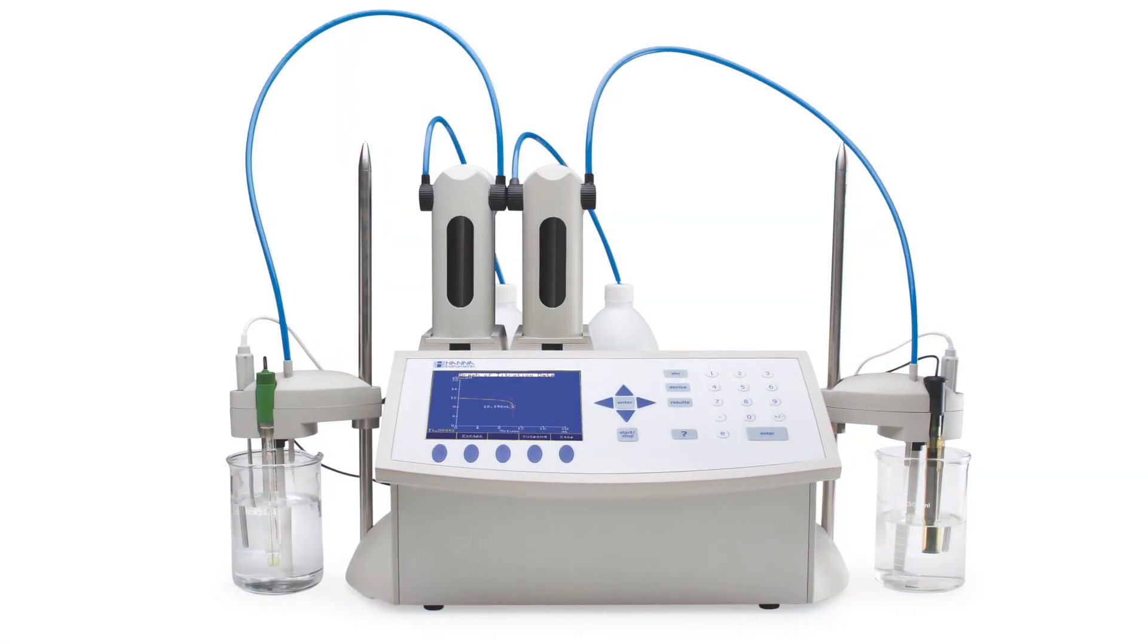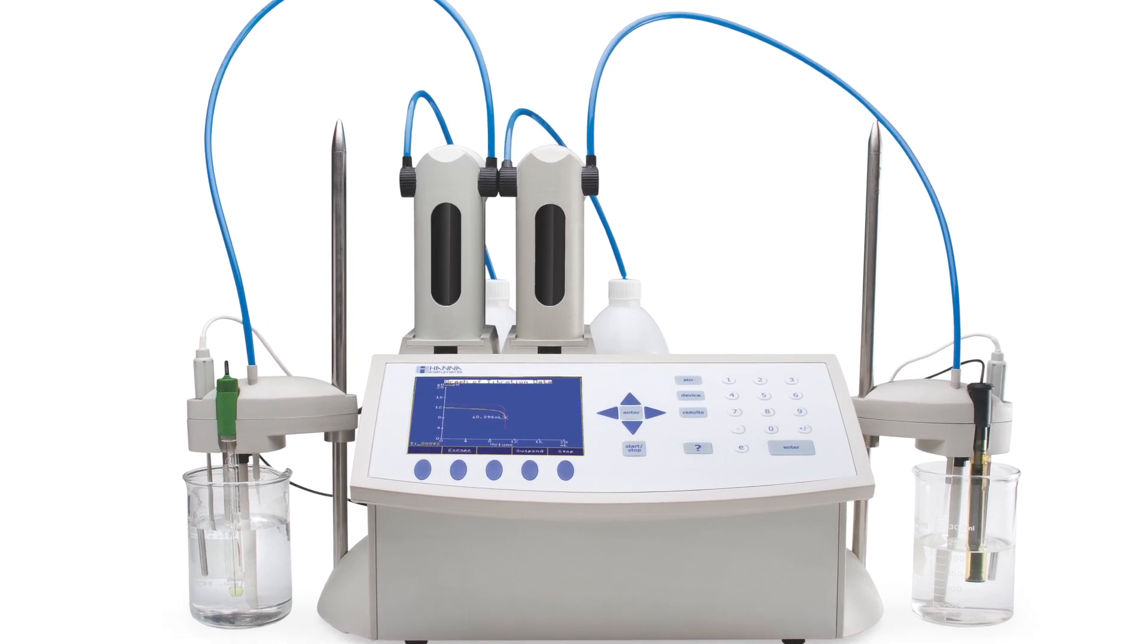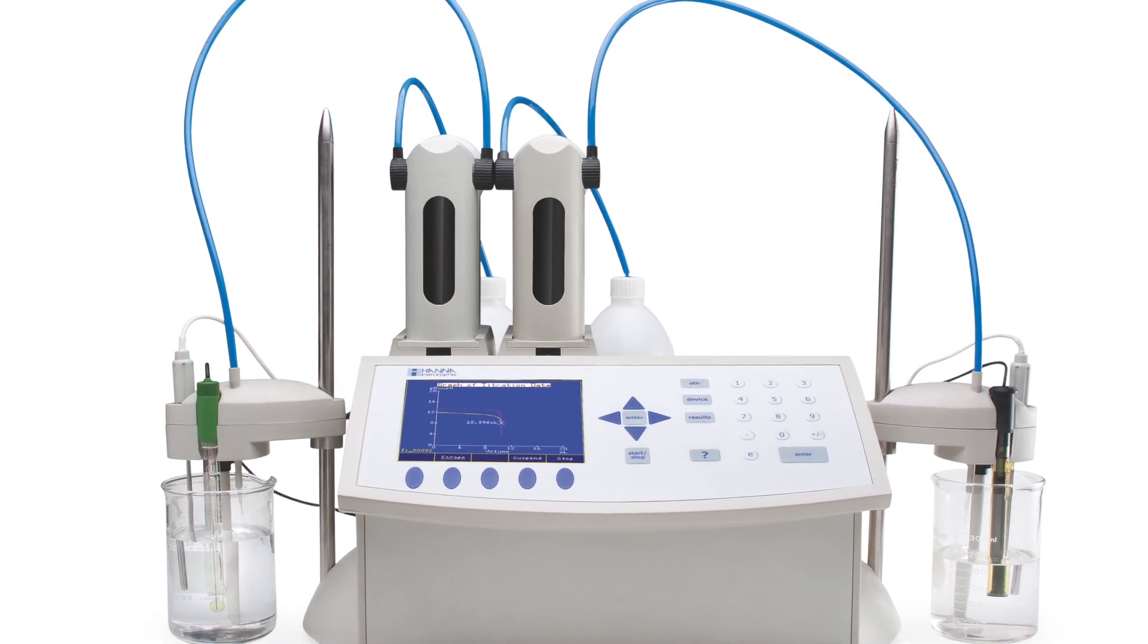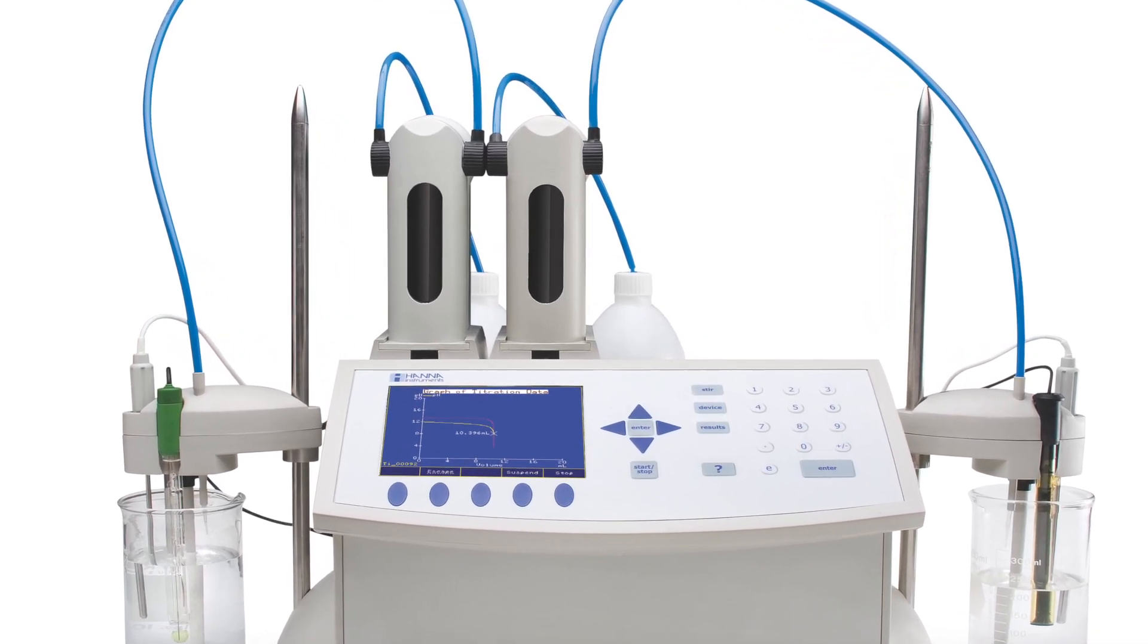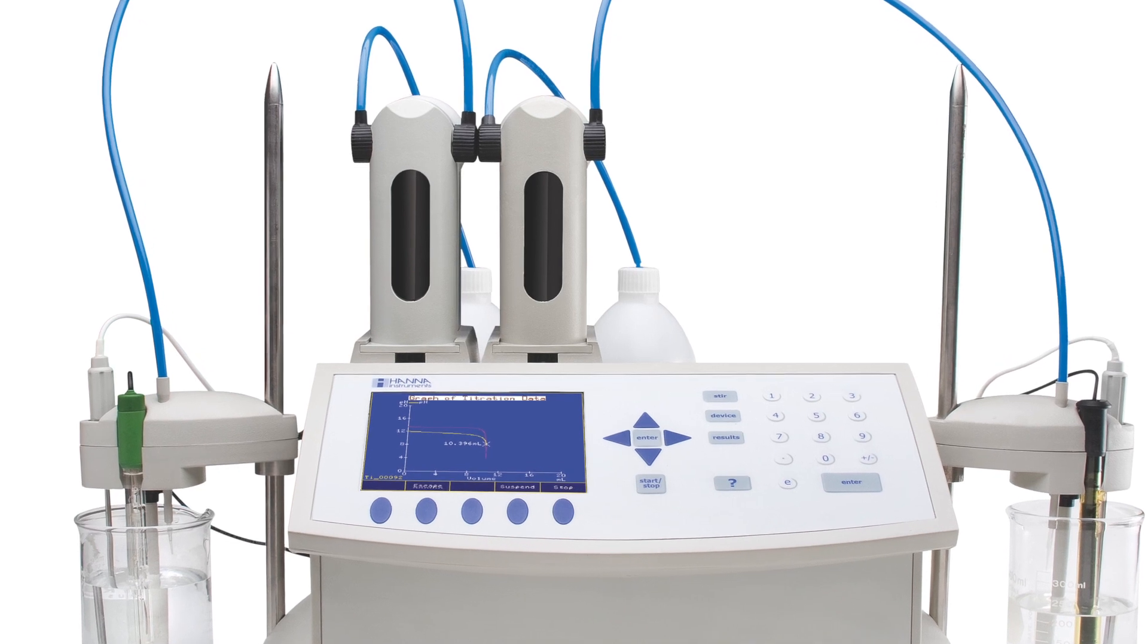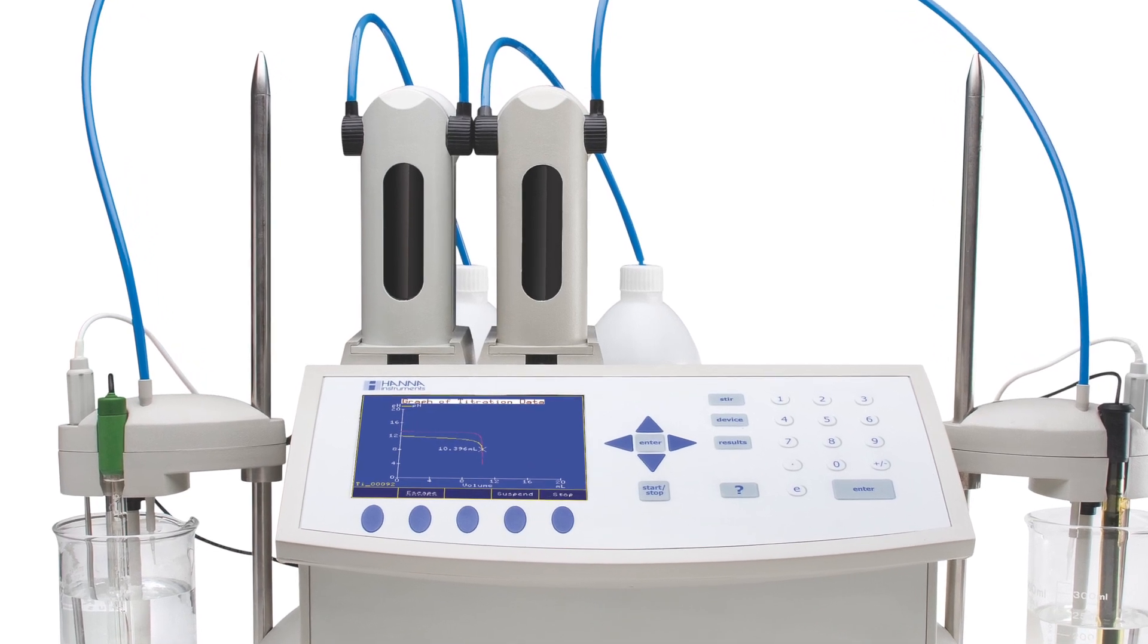The Hanna Instruments Automatic Titrators can store up to 100 standard and user methods, and up to 100 titration reports. Transferring files between the titrator and a USB storage device is fast and easy.